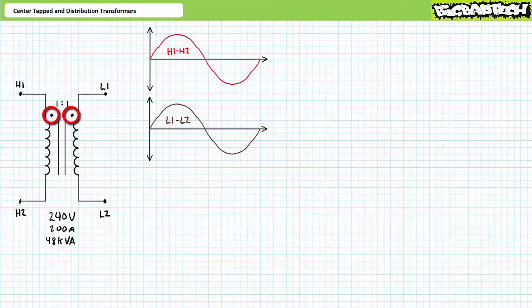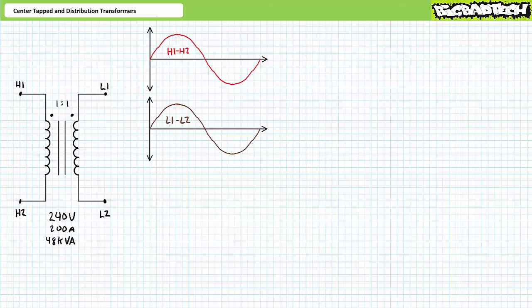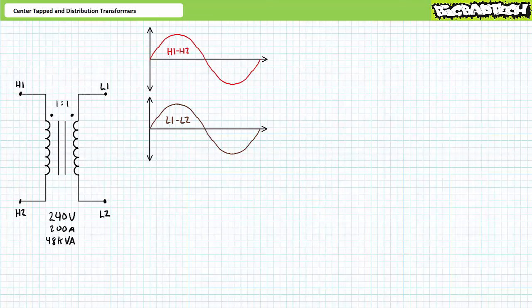If terminals H1 and L1 are identified with a phase dot, this means when H1 peaks positively so does L1. Similarly, when H1 valleys negatively so does L1. Long story short, H1 to H2 is perfectly in phase with L1.